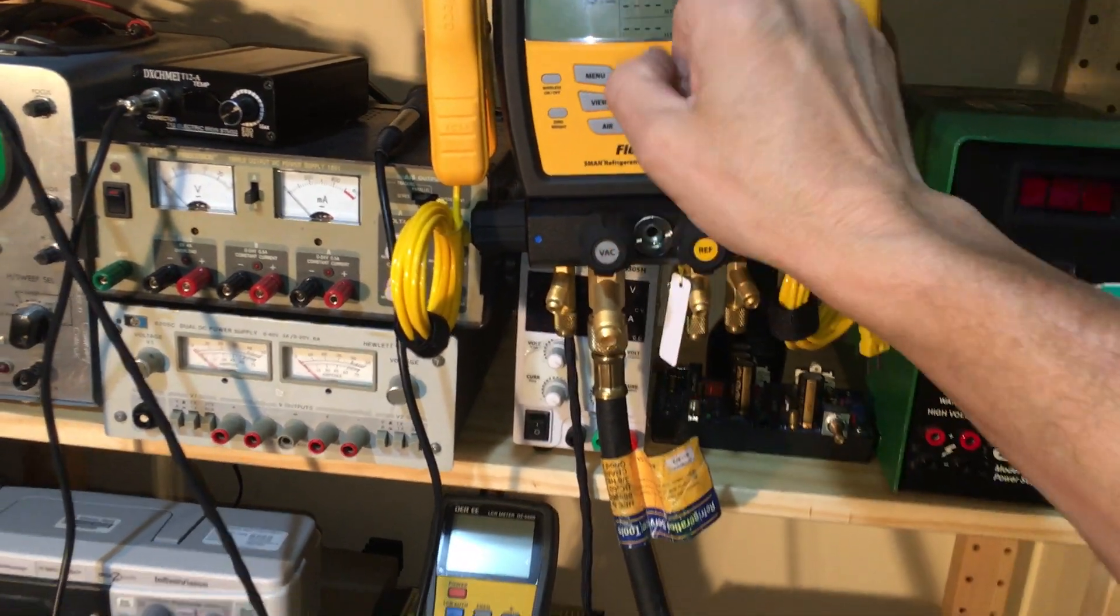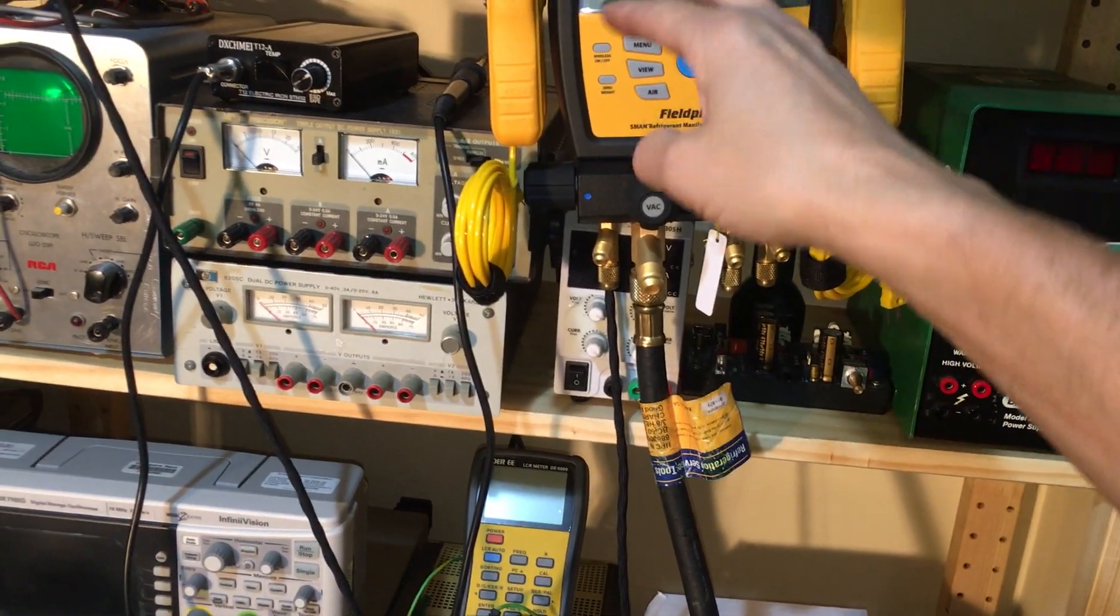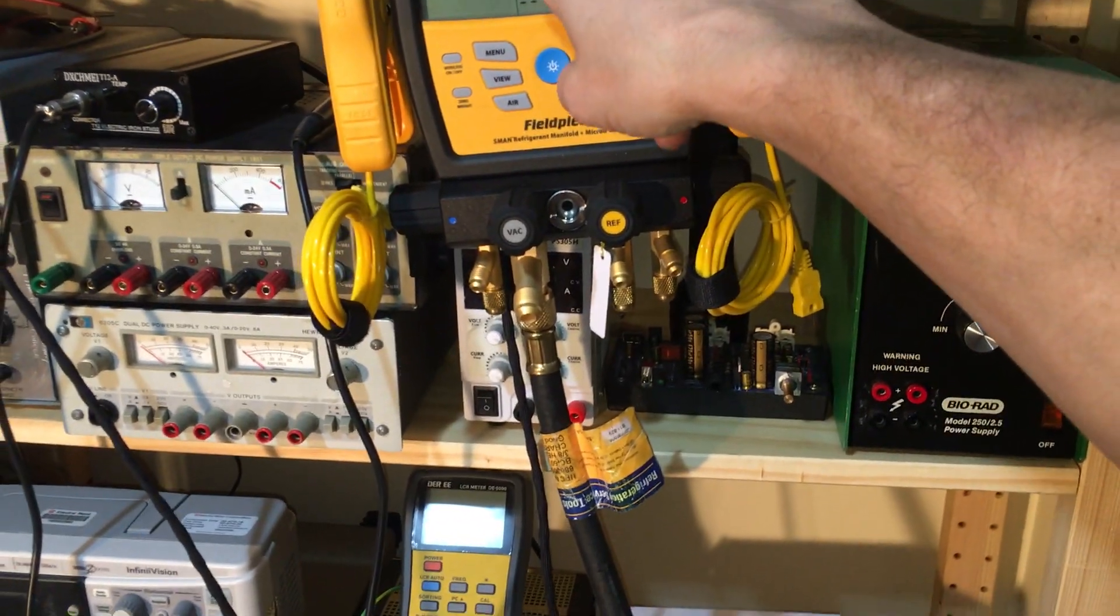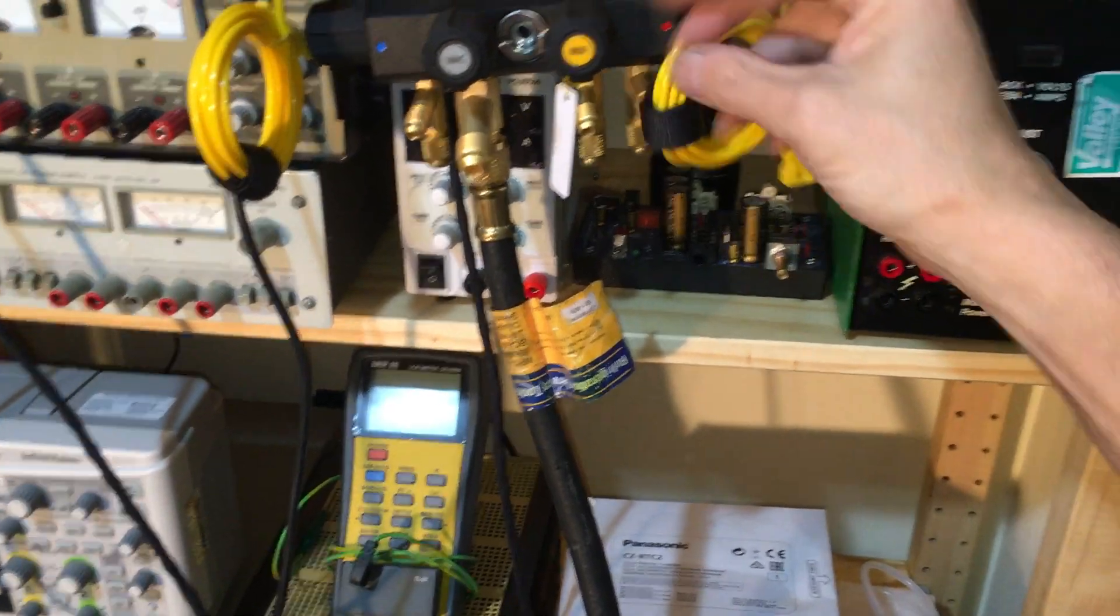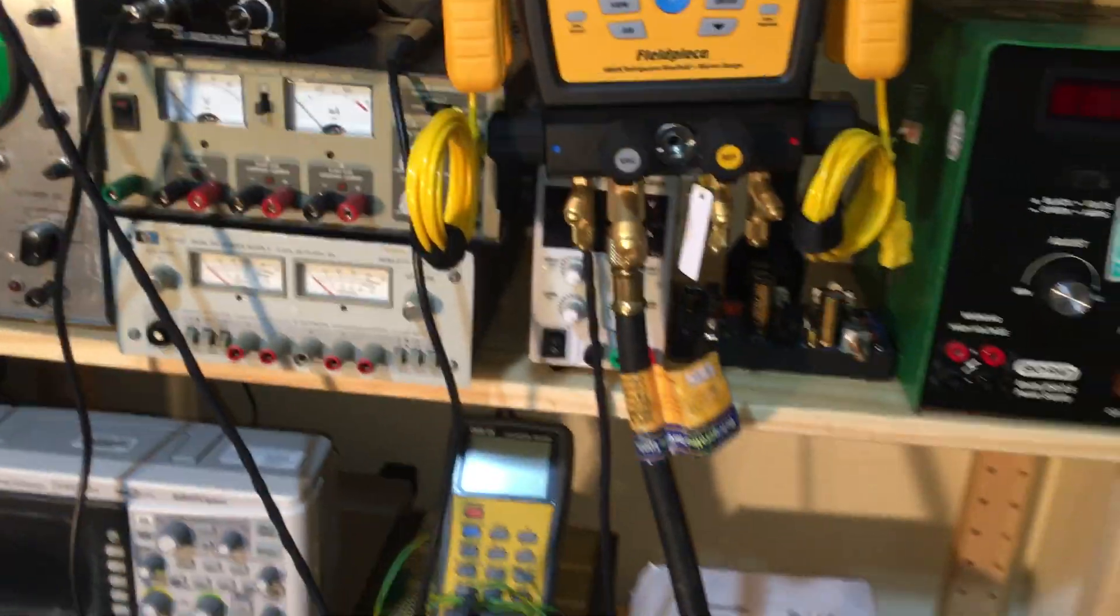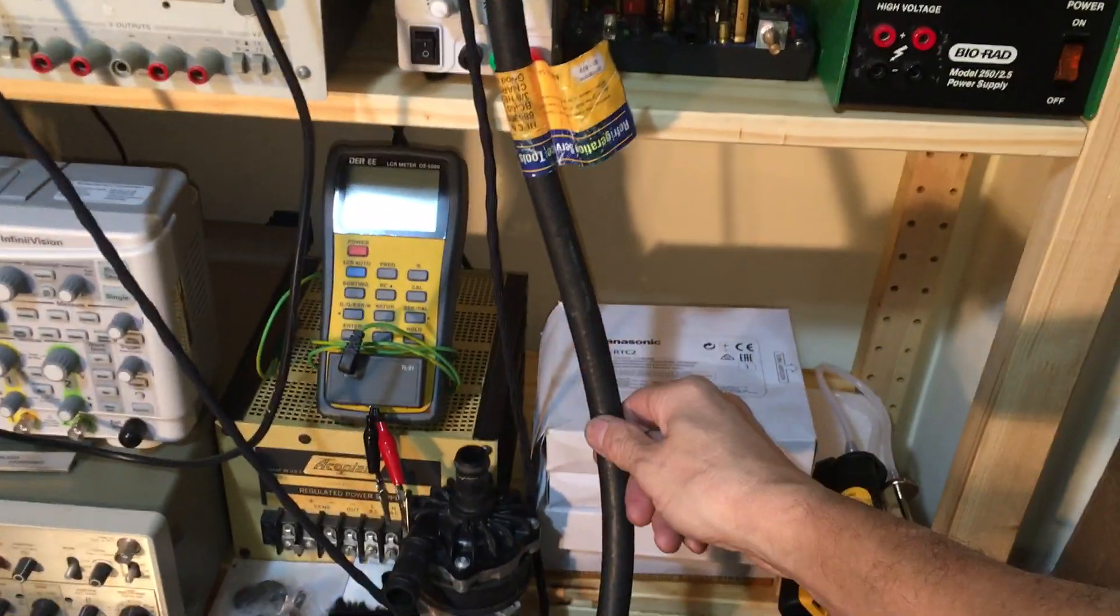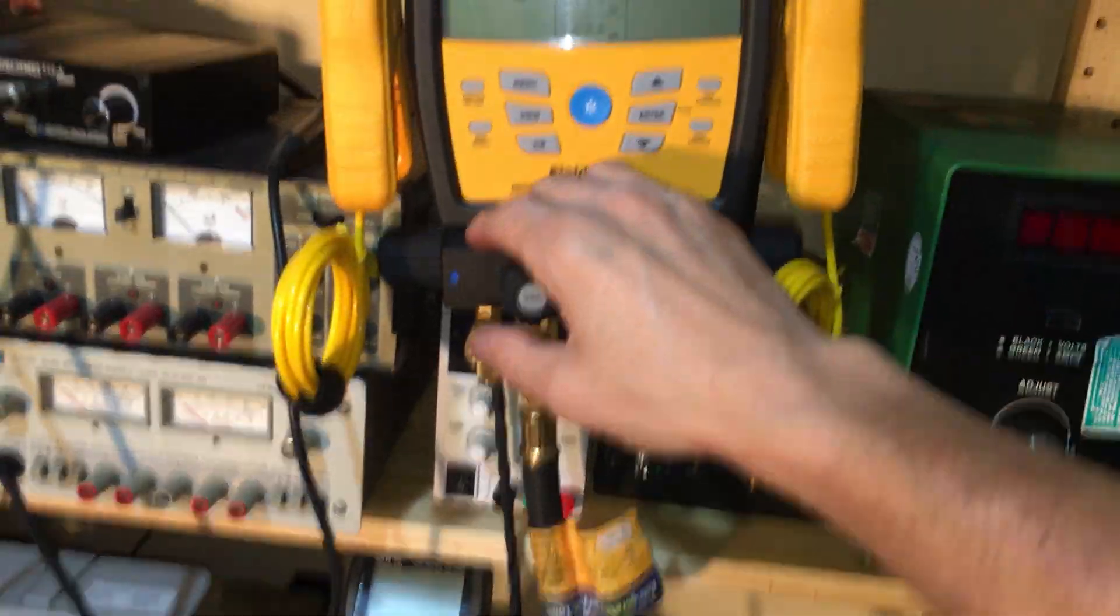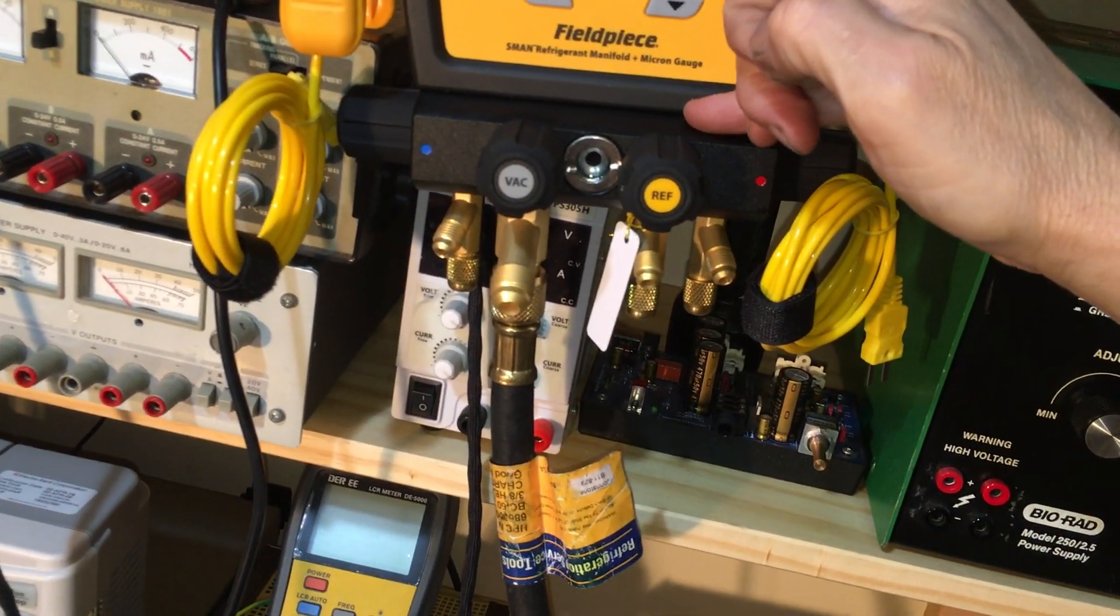So we're at 87. Here's the story: three hours on vacuum, got it down to roughly 160-140 microns. I turned off the vacuum pump and it rose all the way up to 1900 microns. I checked the valves, moved them in, moved them out. There was no rise. It was staying steady at 1900 microns with this hose shut off. So it wasn't reading moisture boiling out of this hose, just what was inside the valves, everything inside the manifold only.